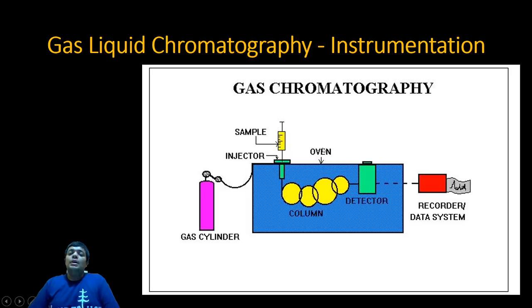Column ovens. The sample in gas chromatography must be converted into and maintained in vapor state throughout the separation process. Throughout the separation process, friends, it means starting from the injector up to the detector, there should not be any place where the temperature changes. So all these components should be inside the column oven. Injector connections, column, detector connections are all inside the oven. The range of the oven should be from 40 degrees to 400 degrees Celsius.